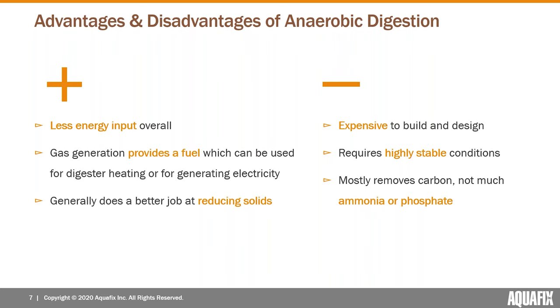The upsides are that a well-running digester doesn't need a lot of energy input because the biogas can fuel heating or electricity generation. There's no aeration required and mixing is fairly efficient overall. Anaerobic digesters also do a good job reducing solids and are more complementary to an activated sludge process than aerobic digesters — they can degrade substrates not efficiently degraded aerobically, like fats, and achieve higher total volatile solids destruction.